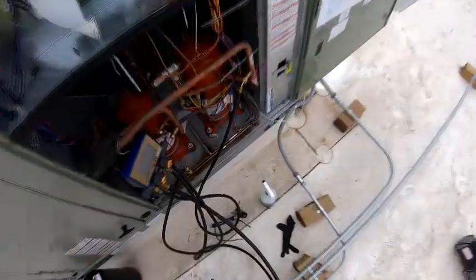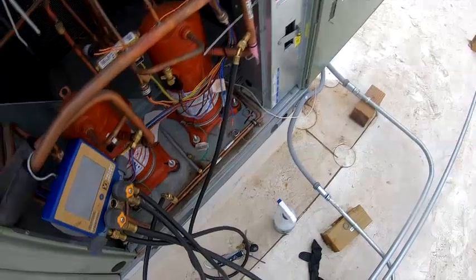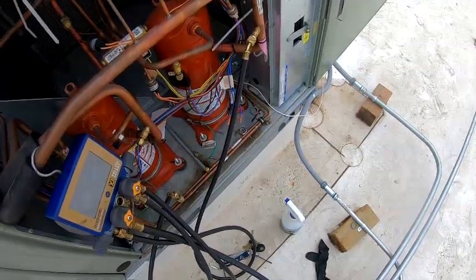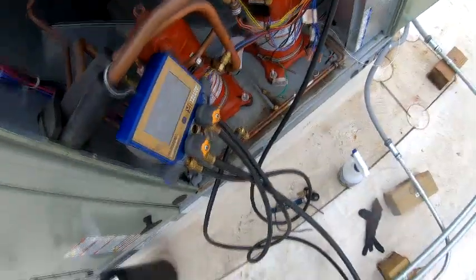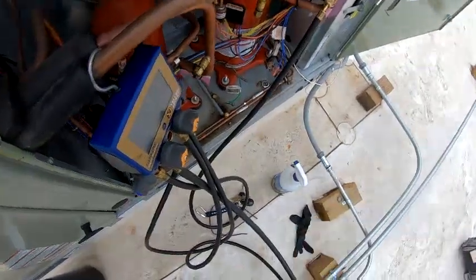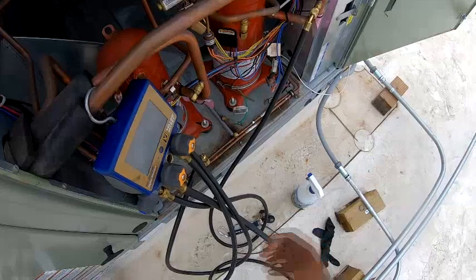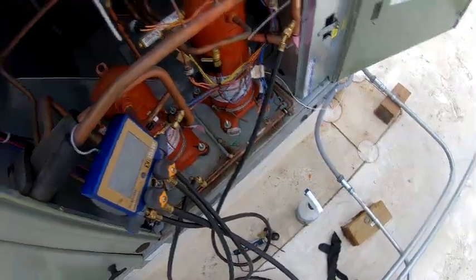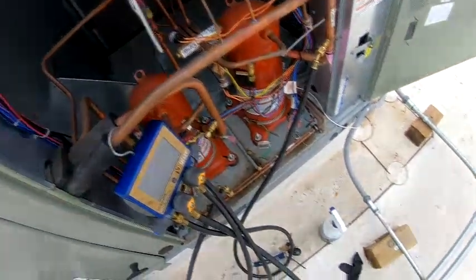An old school guy taught me that a while back, dog. I remember when I first got started they told me you had to put a whole bunch of nitrogen in there, like 300 PSI, to find the leak. Sometimes you do, if you want to do a pressure test or something like that. But to find small leaks, I say start with just cracking it a little bit, then try to find it. If you can't find it, then maybe you want to pressurize it a little more.